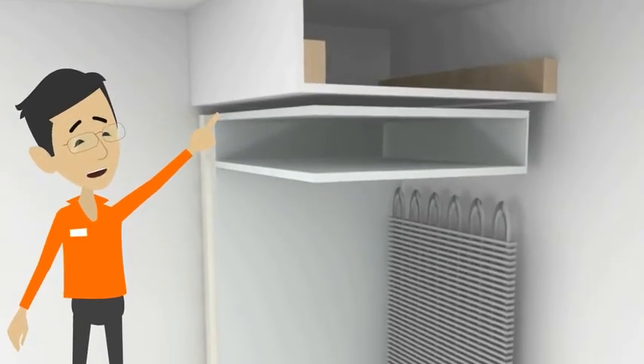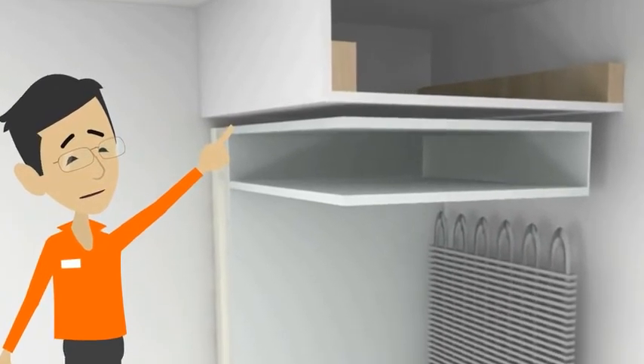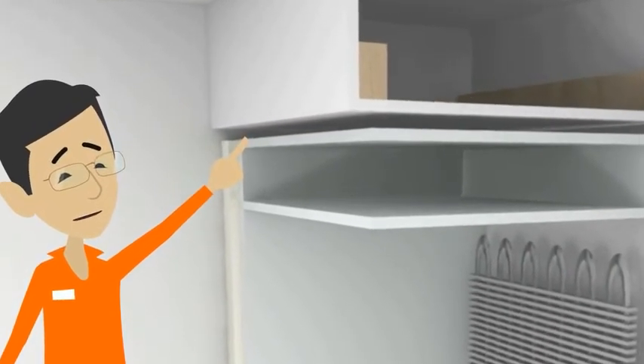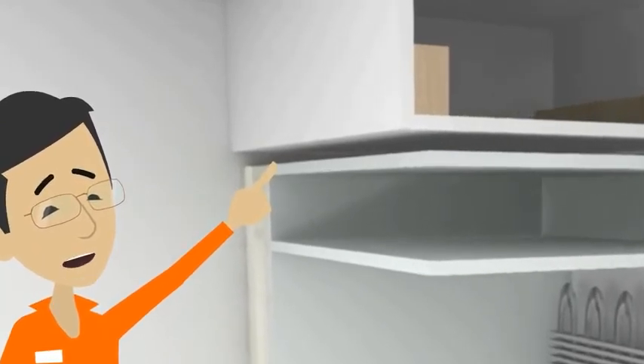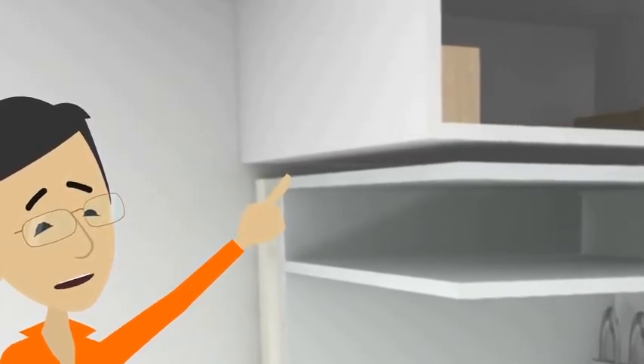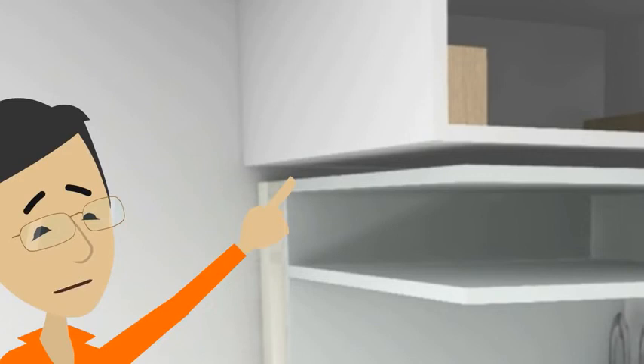When installing a bulkhead over an appliance, please leave a 2 centimeter gap. It is also good design practice to leave the same distance from the face of the doors to the face of the bulkhead. You will need a 2 centimeter by 100 centimeter gap to achieve the minimum requirement of 200 centimeter squared.